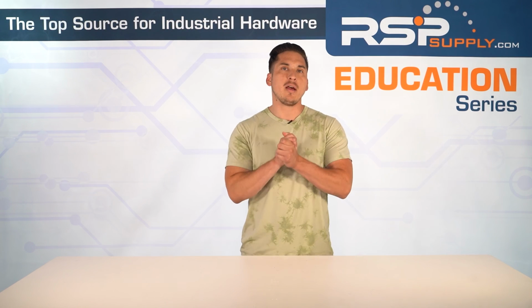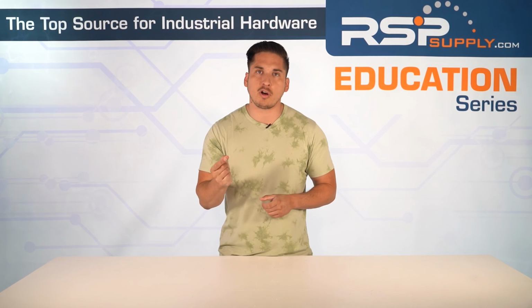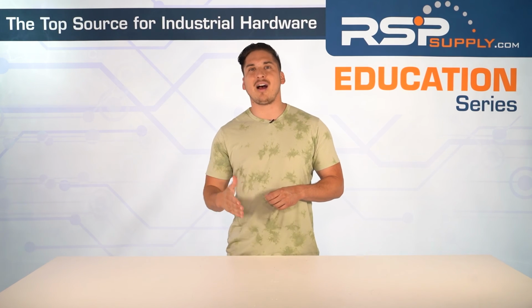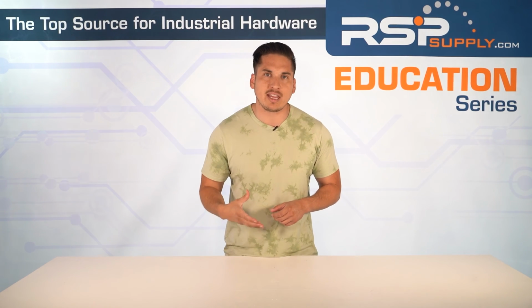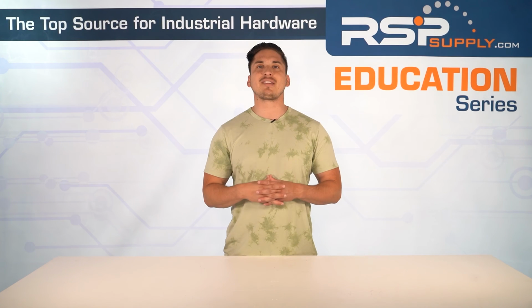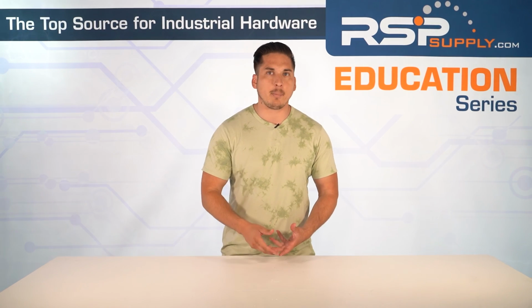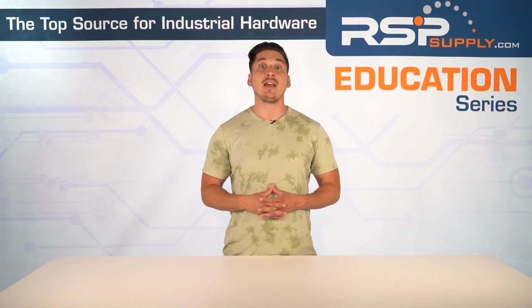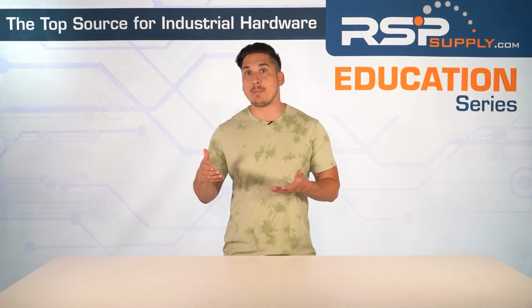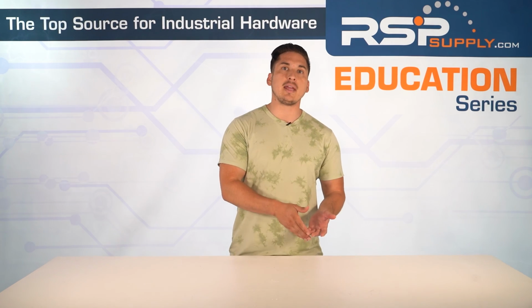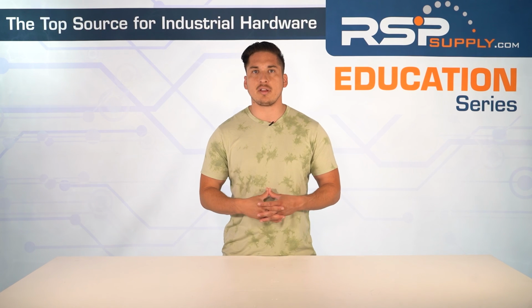So let's recap. Control circuits are the brain. Start-stop logic, sealing contacts, and overload protection keep things running. Protection elements like breakers and relays are the muscle that stop disasters before they happen. And picking the right contactor, that's the key. Right? You need to match the ratings, the duty, and environment to avoid costly failures.